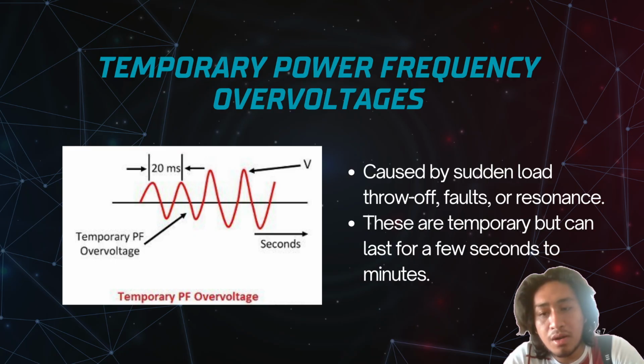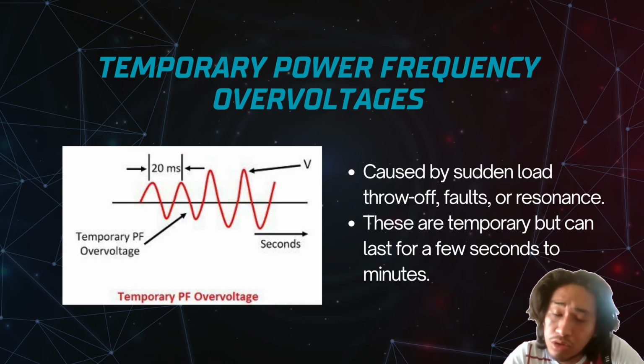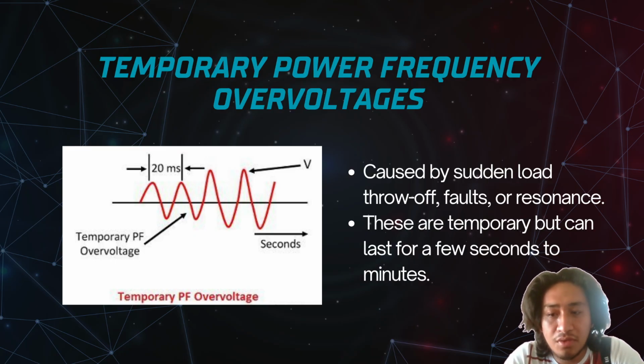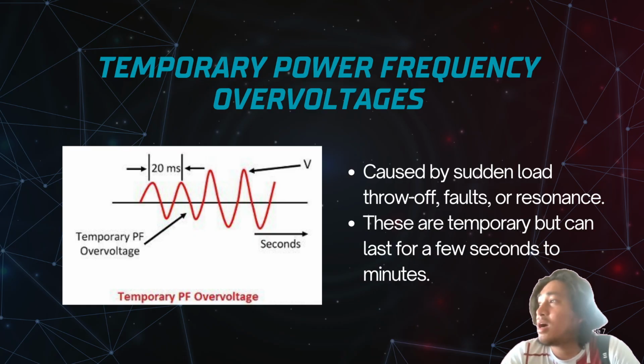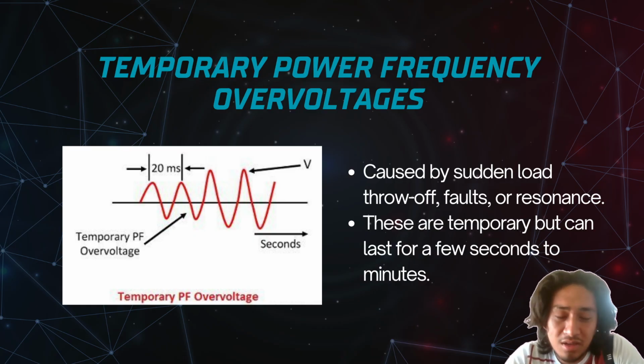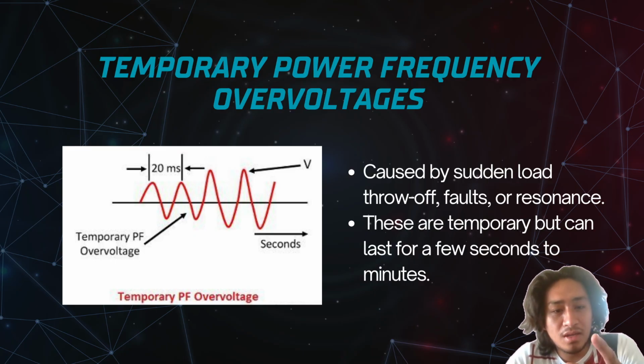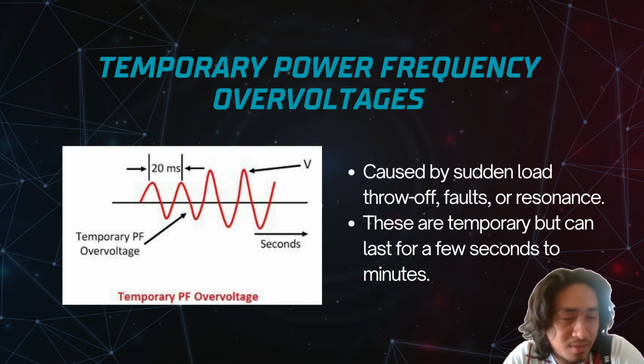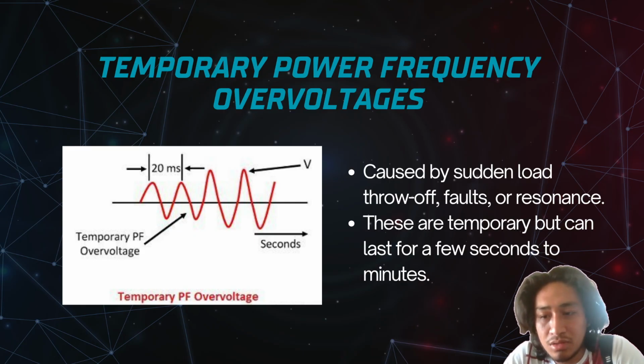the line. So temporary power frequency overvoltages, also known as TOVs, are long-lasting voltage spikes lasting seconds or even minutes at normal grid frequency. They occur when the grid balance is lost due to faults. So for example, you have three phases, or a three-phase system, and one of your phases has a fault. So the other two phases, the healthy ones, will be affected.